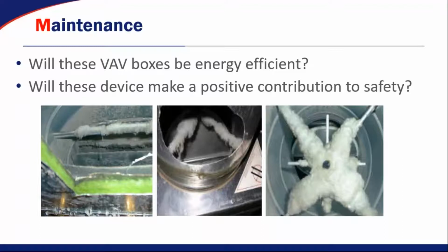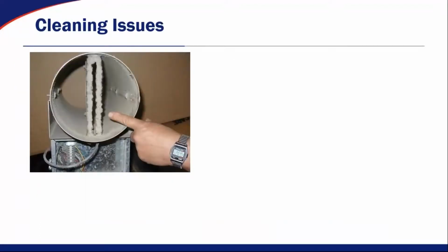So in these particular environments on the exhaust side, trying to maintain differential pressure across a door is very difficult because once the sensors get clogged up, the box works inversely of what its reading is. It's reading a low flow and it's going open to accommodate that change. However, it's not actually showing you what's really going on. People sometimes say, I like a flow measurement device because I know what's going on inside my space. But in these particular environments, you really don't know what those devices are flowing because the flow probes are completely clogged.